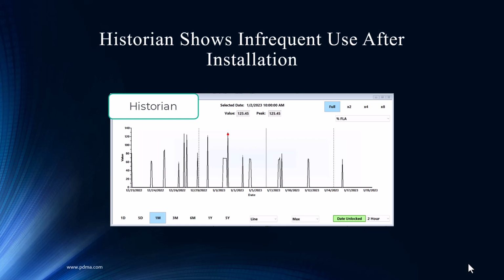At this point you can easily see that the starts and stops on this motor are pretty frequent. That doesn't help the rotor bar situation—it doesn't mean it's going to stop, it just means they need to be aware of that and elevate the concern about rotors. We're extremely excited from an analyst perspective that the Historian is going to provide much broader depth for the first steps in analysis.